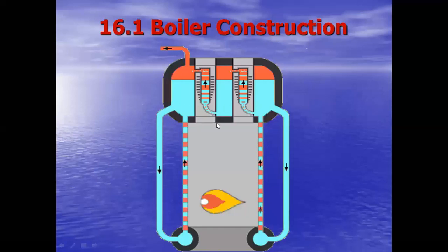This is what we had seen earlier. That time the connection was not very good, so I don't know how many of you were actually able to see this. But this is basically the construction of my Aalborg Sunrod boiler. Here you have the boiler furnace, the flame coming out from the burner. Around the furnace are these small diameter water tubes. All these water tubes are touching each other, so there is no flue gas which can pass out of the furnace. All these tubes basically form a wall around the furnace.